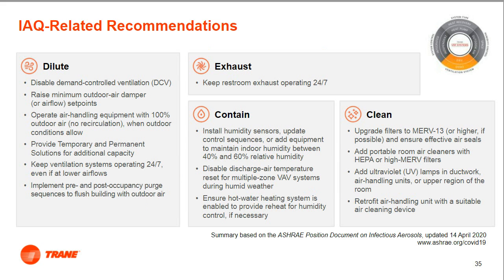Dilution is used to increase the amount of fresh air in order to make sure that the stale air is less likely to be recirculated into a space. By disabling demand control ventilation, the air supply will remain consistent throughout the day, instead of relying on the level of occupants in a space to determine the outside air requirements. It is also recommended that when a building is unoccupied at either the beginning or at the end of the day, that the system purge be done by ramping up the outside air supply to remove any remaining particles that may be lingering in the air.